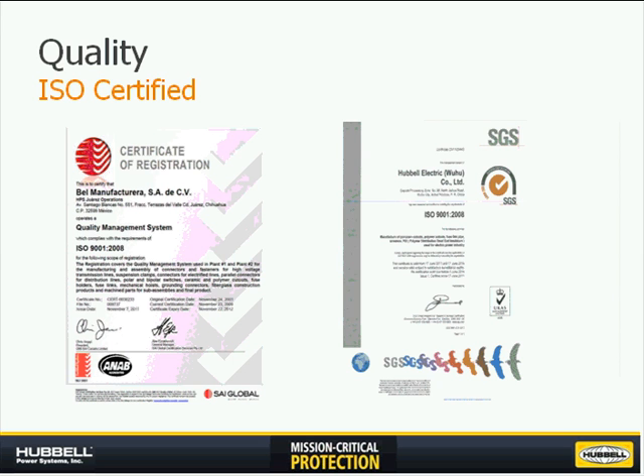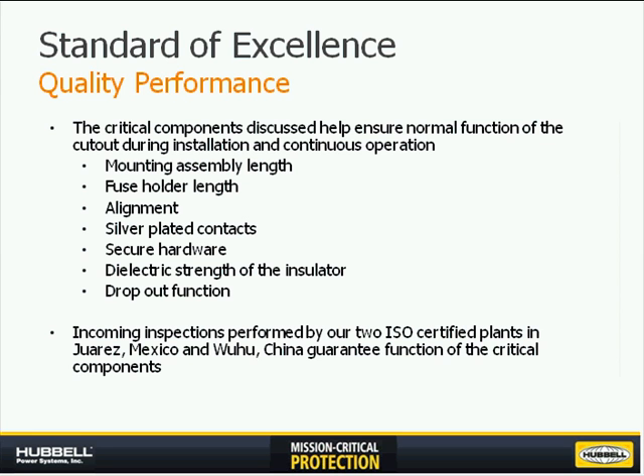Both of our plants in Juarez, Mexico and Wuhu, China are ISO 9001 certified. To summarize, the critical components for practical application of the cutout are: mounting assembly length, fuse holder length, alignment, silver plated contacts, secure hardware, dielectric strength of the insulator, and dropout. All of these checks, with the exception of dielectric, are performed 100% in our plants. Dielectric is more of a routine test.